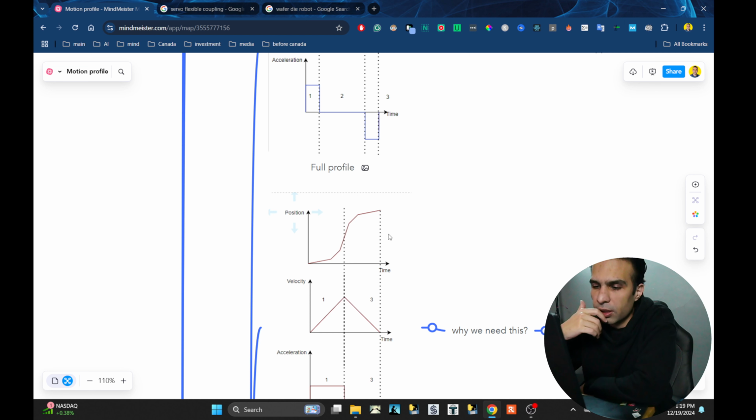The reason that I'm choosing triangle drive is that when you achieve the same thing, it means that you want to achieve the same performance. When it's a full profile, you have to accelerate higher. It means that you have to put more torque and those kind of things. So torque is always an issue, because you are fighting with inertia, you are fighting with mass. So that is very energy consuming, power consuming.